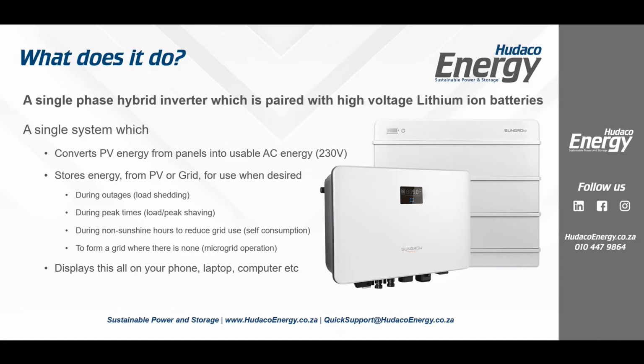Number 2, during peak times, so we can do load or peak shaving. Not so commonly used because we don't have a time of use tariff on residential yet, but that may come. And of course, some clients maybe want to have a bigger demand than the supply that they have, so this will allow for that. Number 3, to reduce grid use or reliance on grid during sunshine hours, which we call self-consumption. And in fact, we can do it after hours using self-consumption as well with the batteries.